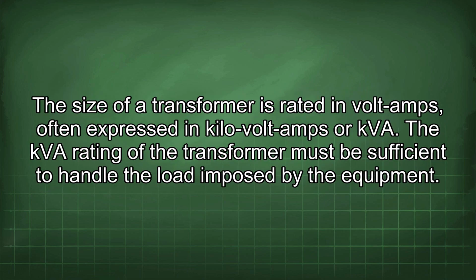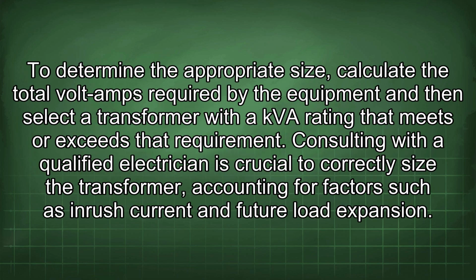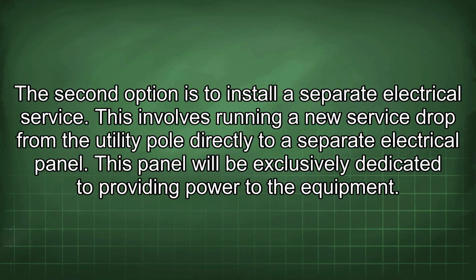The size of a transformer is rated in volt amps, often expressed in kilovolt amps or kVA. The kVA rating of the transformer must be sufficient to handle the load imposed by the equipment. To determine the appropriate size, calculate the total volt amps required by the equipment and then select a transformer with a kVA rating that meets or exceeds that requirement. Consulting with a qualified electrician is crucial to correctly size the transformer, accounting for factors such as inrush current and future load expansion. The second option is to install a separate electrical service.